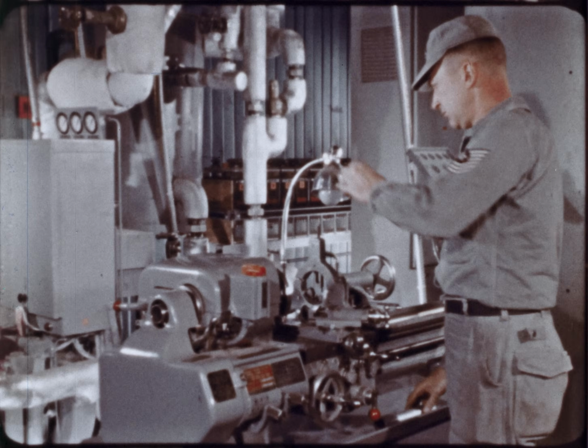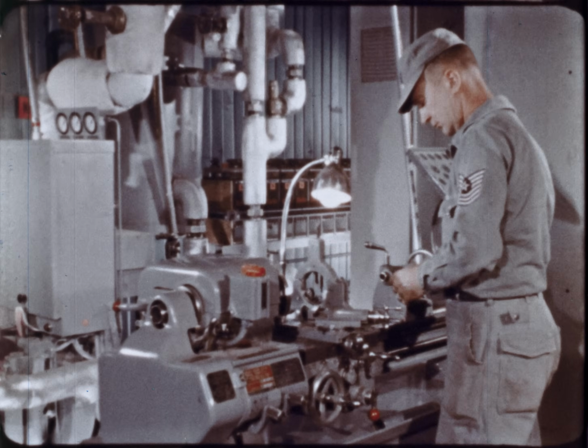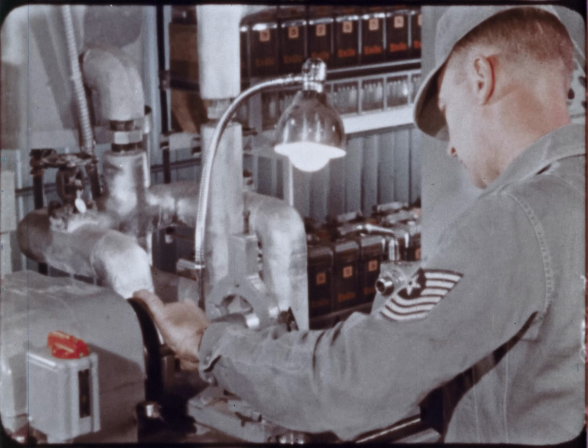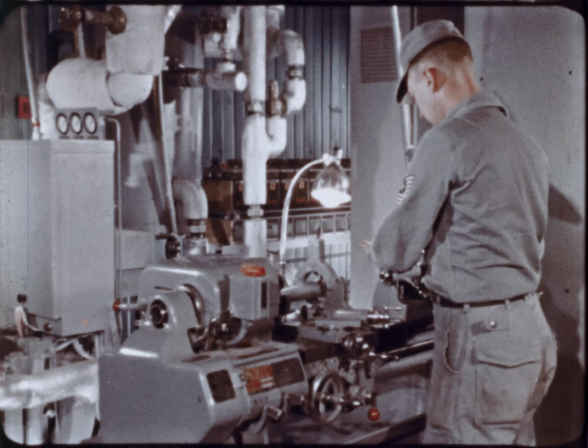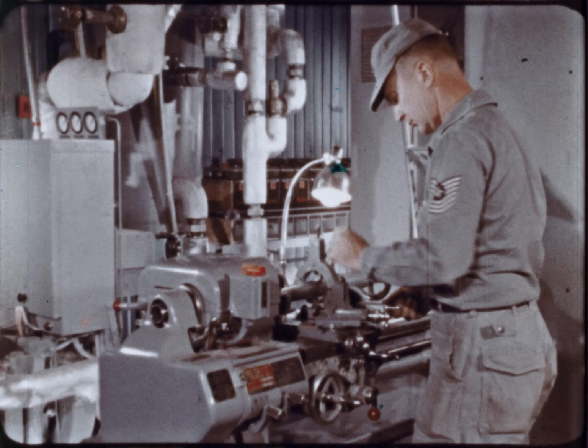The maintenance package holds standby generating equipment and a shop with a grinder, welder, and lathe. Almost any general repair to the plant can be made here. By specification, the plant can only be shut down 21 days per year, and of these, only 6 are scheduled for annual plant shutdown. The shop will help the plant to meet its shutdown specification.